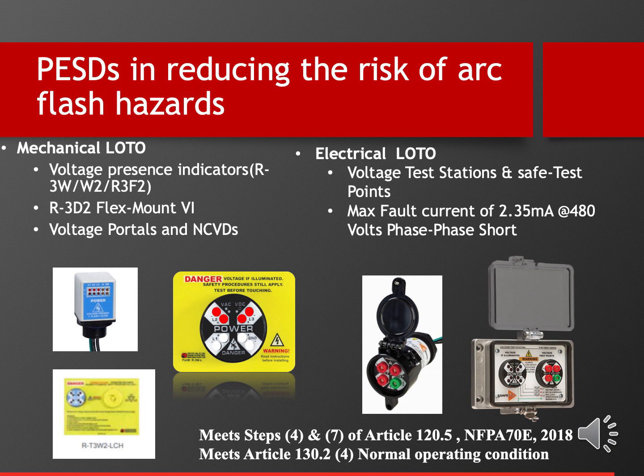The voltage indicators you see on the left side are primarily used in mechanical lockout tagout for verifying the voltage presence, such as lost phase and stuck blade conditions. We have several options to meet your unique needs in various configurations, and they all add an additional layer of risk control for your mechanical lockout tagout to verify the voltage presence. This product again meets step 4 of NFPA 70E article 120.5.